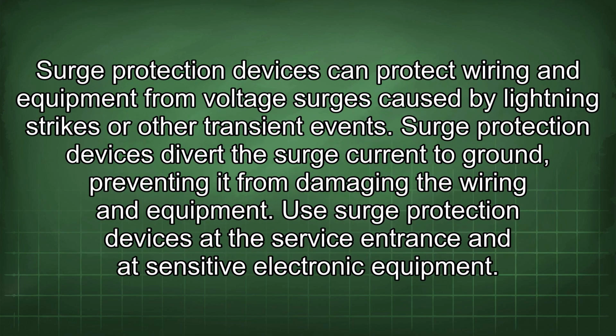Surge protection devices can protect wiring and equipment from voltage surges caused by lightning strikes or other transient events. Surge protection devices divert the surge current to ground, preventing it from damaging the wiring and equipment. Use surge protection devices at the service entrance and at sensitive electronic equipment.